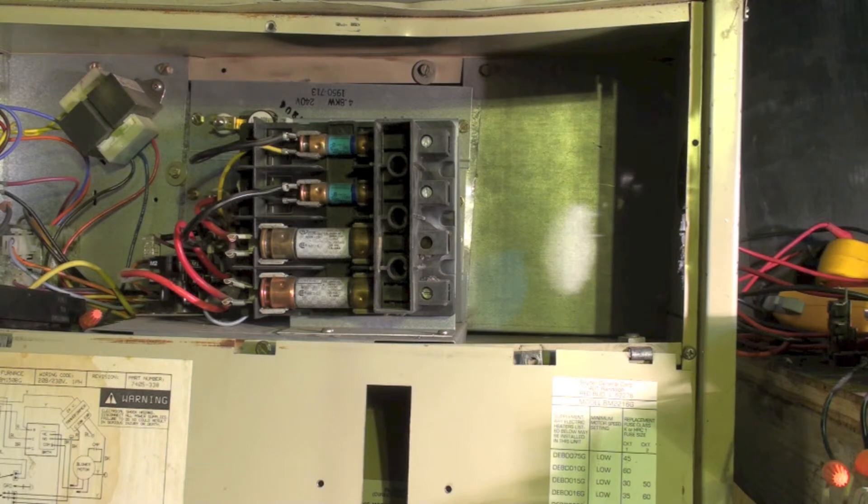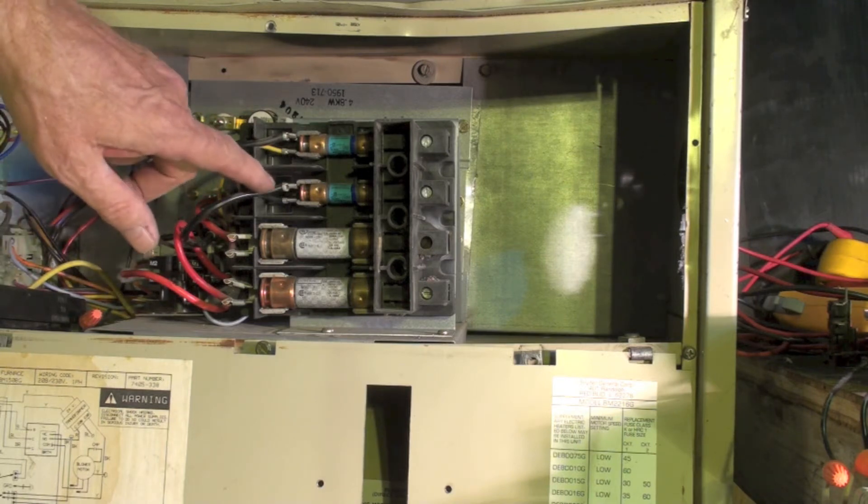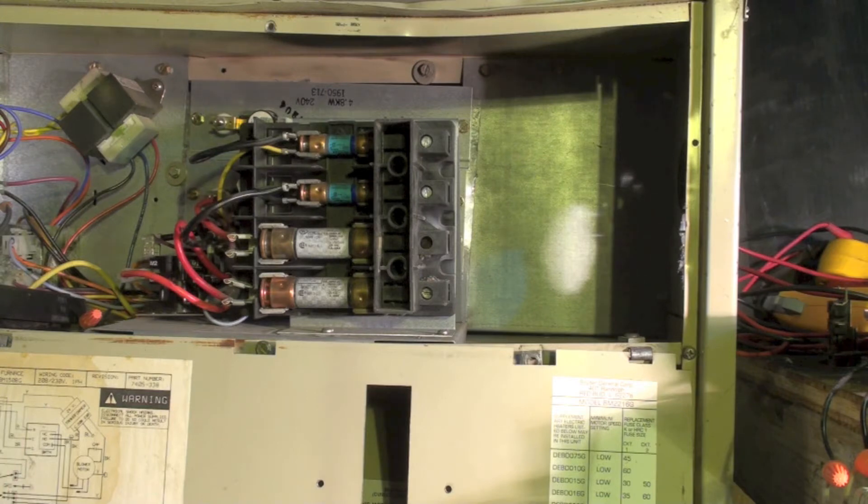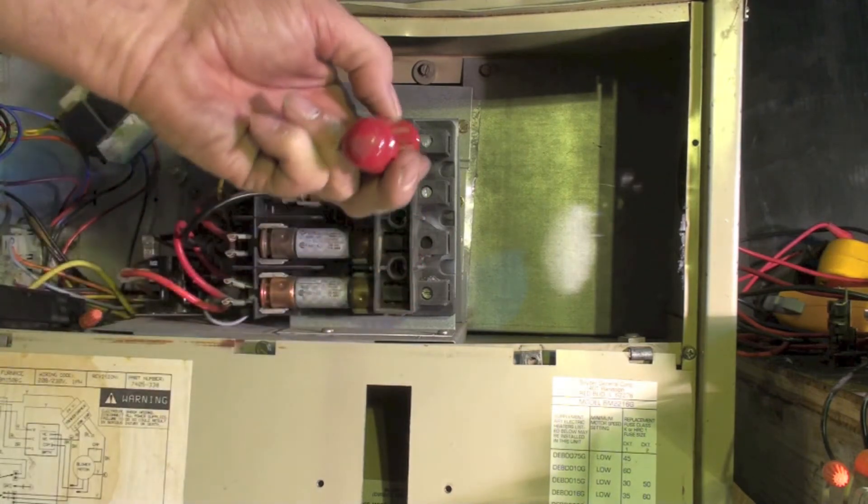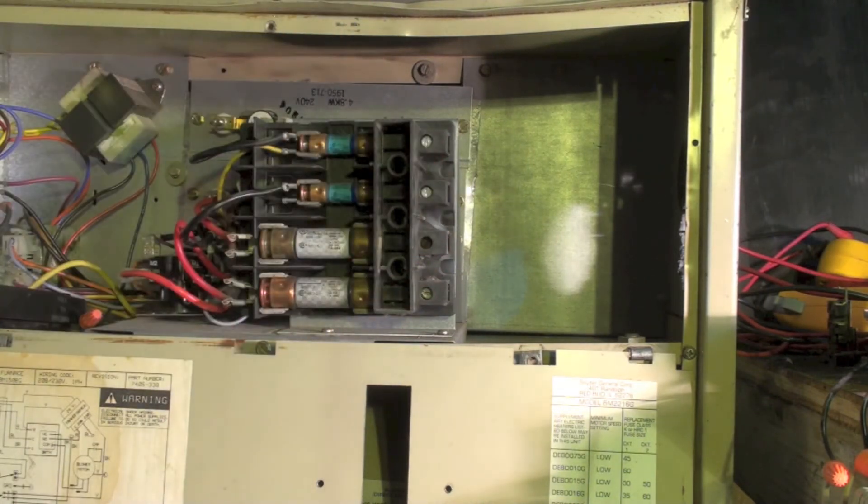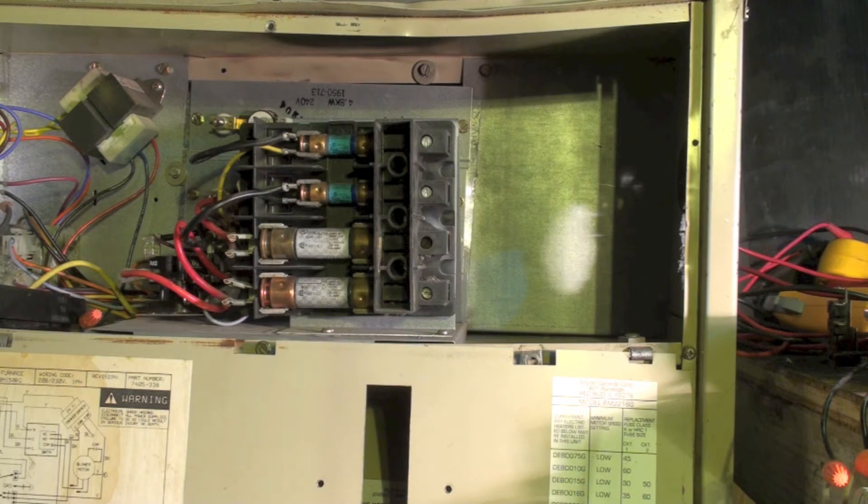Look for burned ends on the wires, that sort of stuff. Remember, pulling this out, which pulls the power to the furnace, does not cut the power here. So you got to go to the panel and shut it off in the panel. Anyway, tight connections, especially aluminum - aluminum was supposed to have the glop on it.